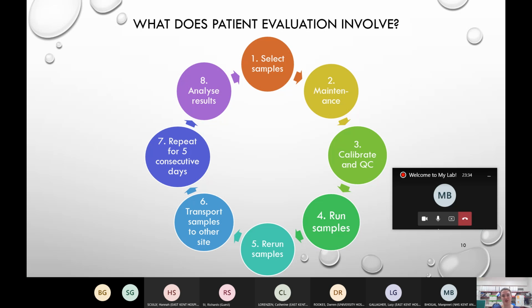And the next thing you do on the first day of patient evaluation is set up your analyzer, do the daily maintenance, and check that the reagent levels were all okay. And then you would calibrate and QC the analyzer, and you need to do that for every single test that you're going to run that day. So every day I'd be doing the general chemistry, immunology, gentamicin, vancomycin, that was on that list on the previous slide. And of course, it must all pass and be well within the set reference ranges that we have made for that analyzer. And then the next stage is to run all the samples, all 90 of them.